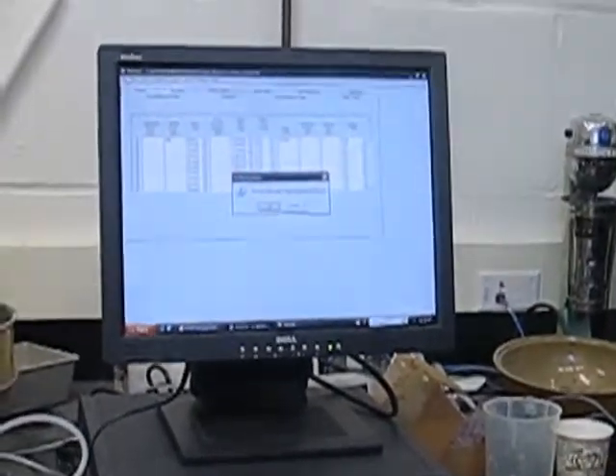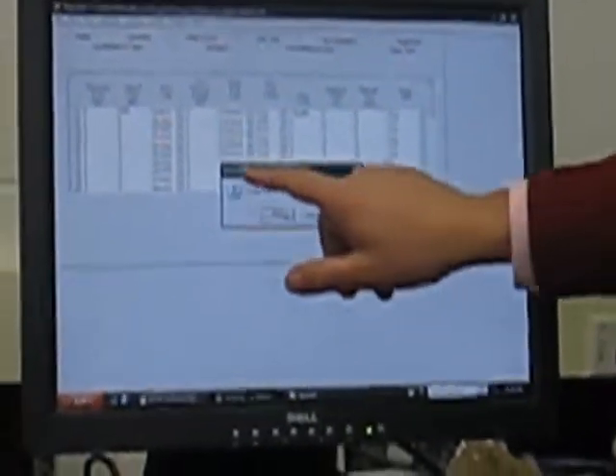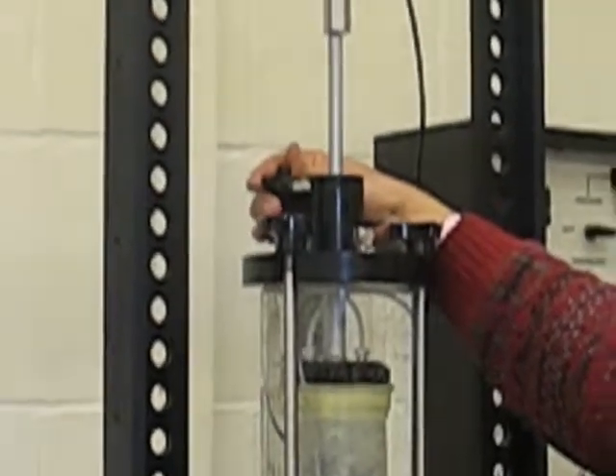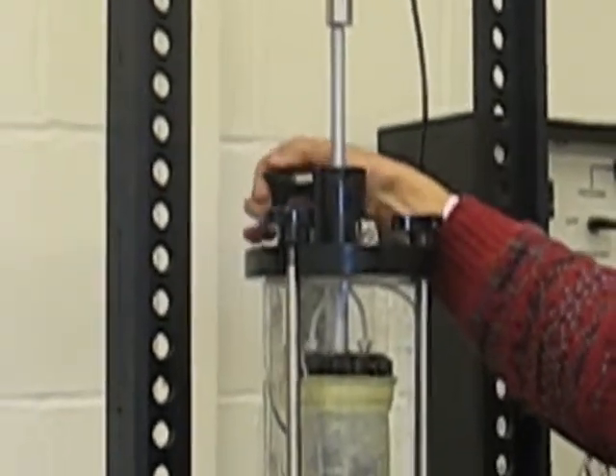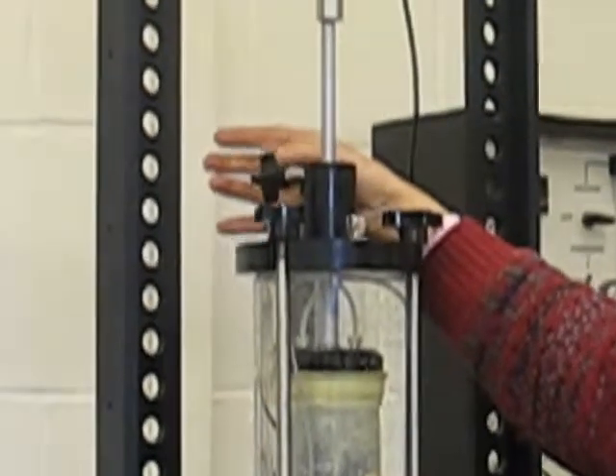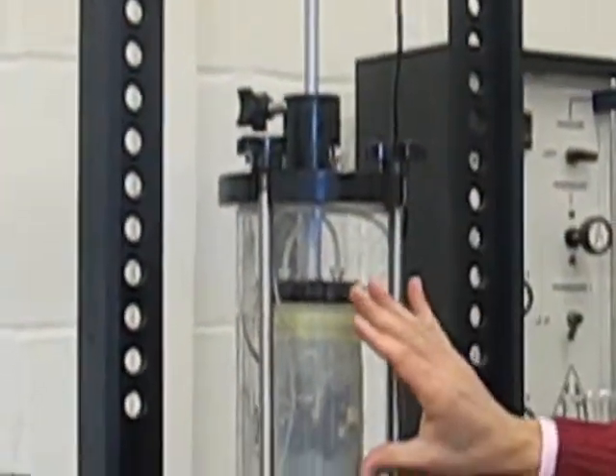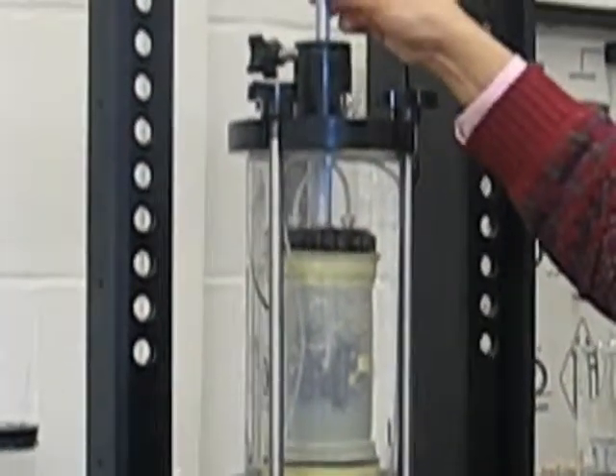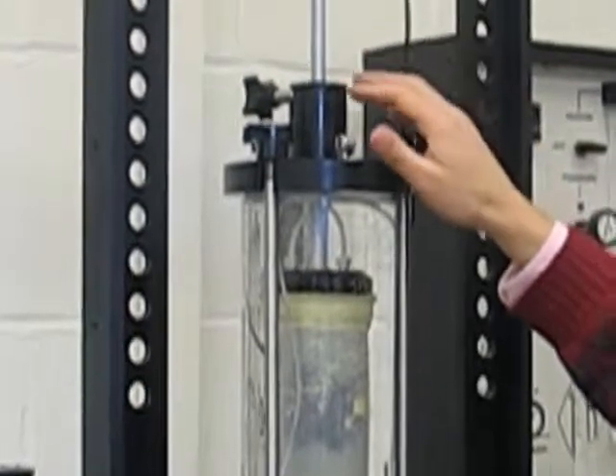The next thing that shows up, we're going to say okay because we know that the gap is closed. Now the next message on the screen is unlock piston, so you go and you unlock the piston. You're measuring the sample properties, and then you hit okay. And the test automatically starts from beginning until the end.